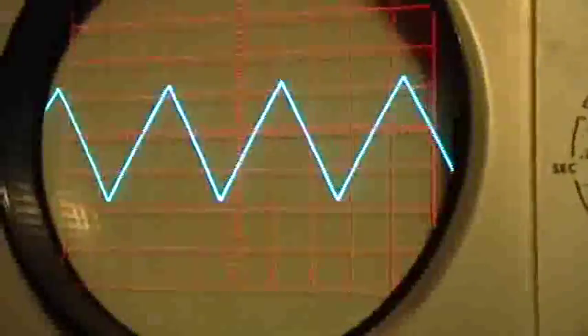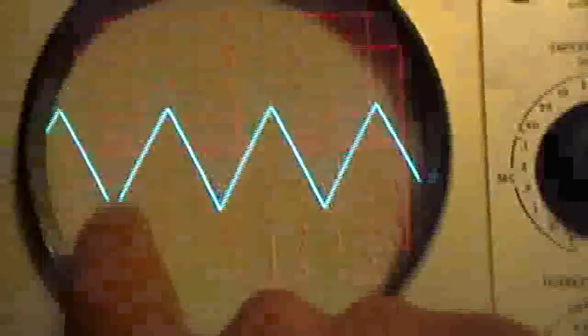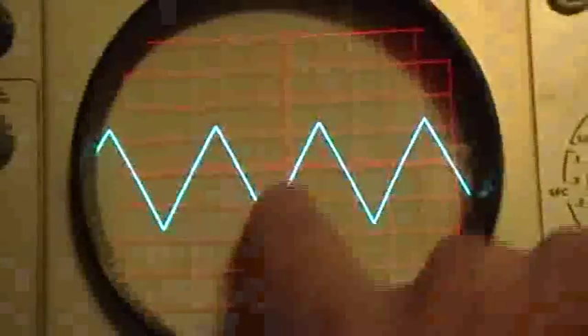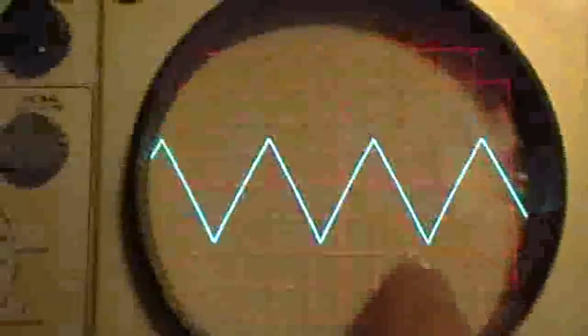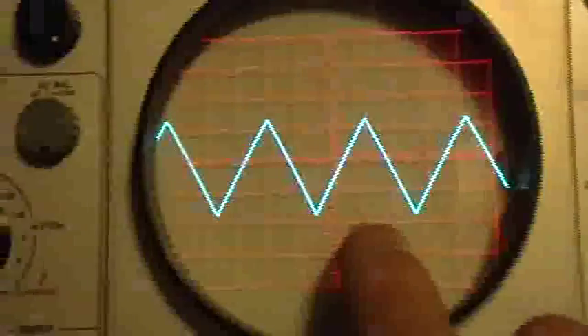Now normally when you display a signal on an oscilloscope, you're looking at the signal waveform itself so you only want to display a few cycles so that you can really see the details and where the zero crossings are. But when you're determining frequency, it's just the opposite. You want, for accuracy, you want as many cycles of that waveform as you can comfortably read on there so that your frequency determination will be accurate. So what I've done is I've just randomly spun the dial on the F43 to give us a random frequency.